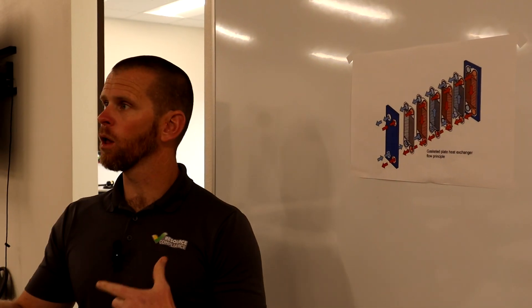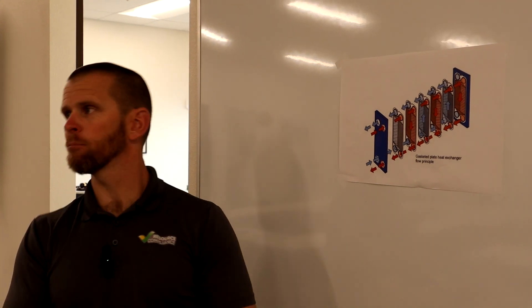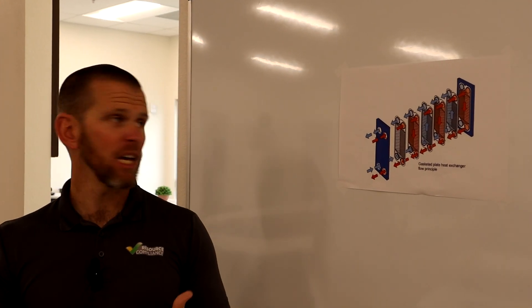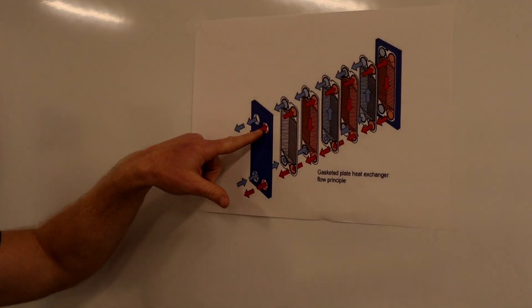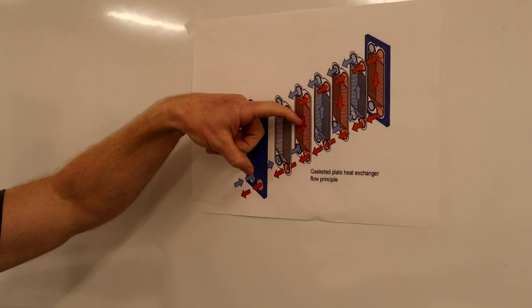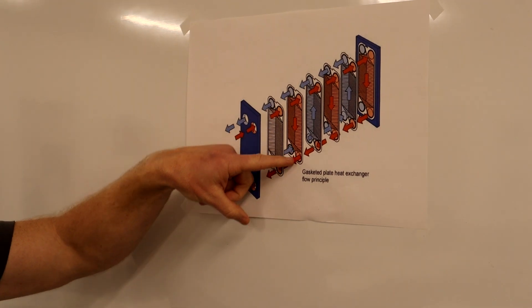Due to the way the gasketing is, it's going to force the flow down one side of the plate and then prevent its flow up the other side. So our warm superheated or hot superheated refrigerant vapor enters and then due to the gasketing it's forced down this side of the plate.